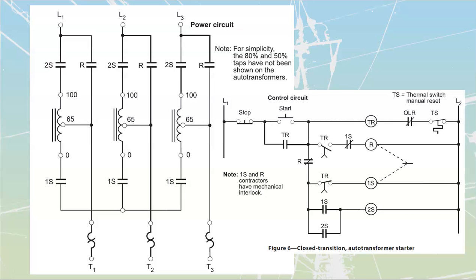That being said, how does this one operate? Well, this one over here is going to have a set of timed contacts. Once again, we see we've got a timing relay that is going to have two associated contacts with it. One of these is going to be normally open, timed to close. The other one is going to be normally closed and timed to open. We should also note that the same timing relay that we have here with timed connections also has one non-timed connection. This one over here is going to be an instantaneous one.